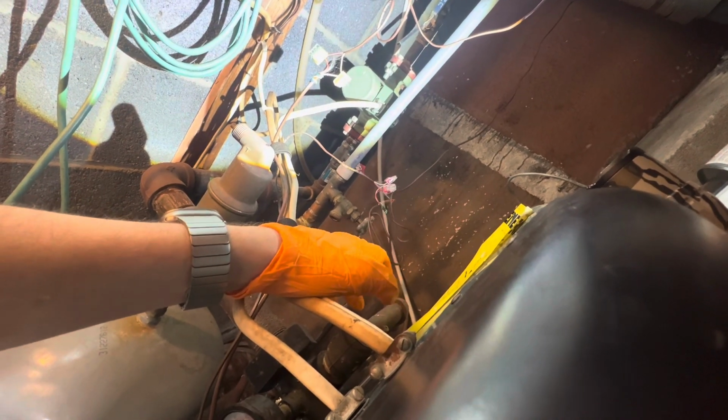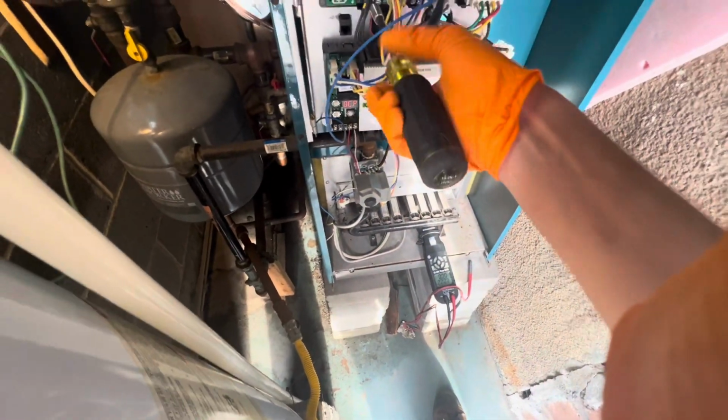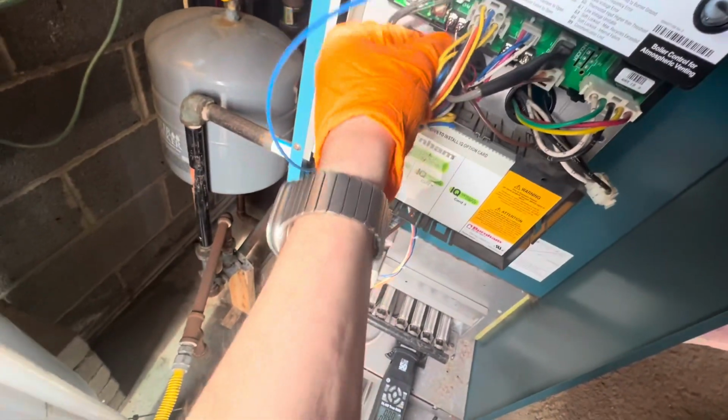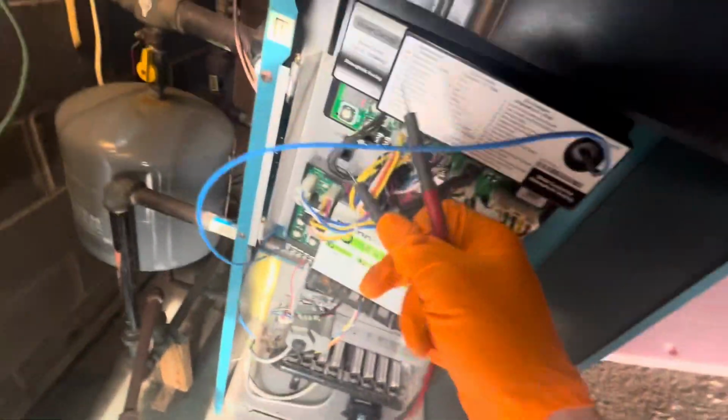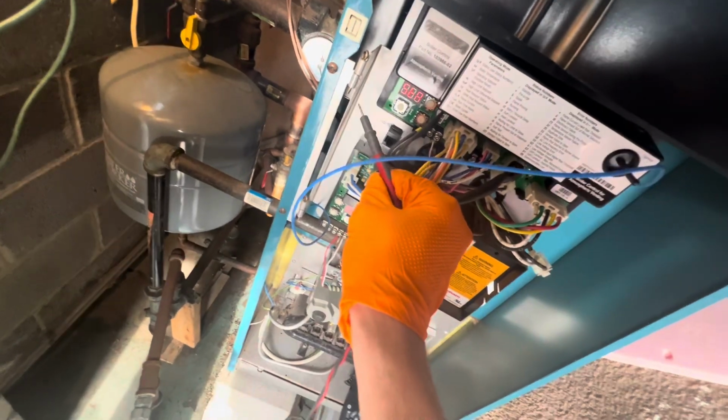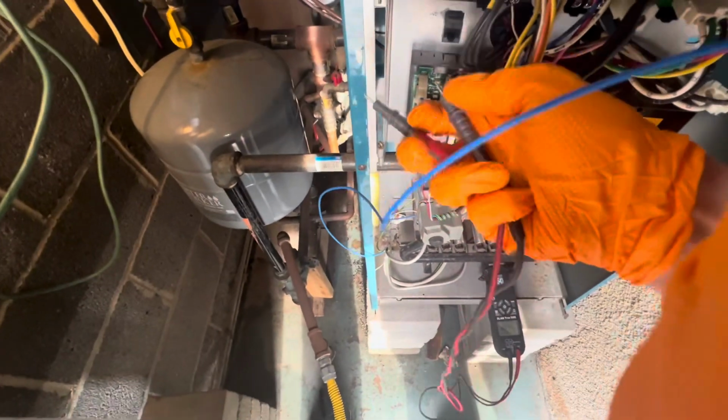So what can I do? I can put the phone down and I can disconnect. No, actually, let's do it right here. Let's disconnect one of our DHW terminals. Right, and our circulator shut off. Good. Okay. Do we currently have a call then? Is the question. I tested the wrong one. Let's go from one end here to ground, which is a little bit tricky to do one-handed.